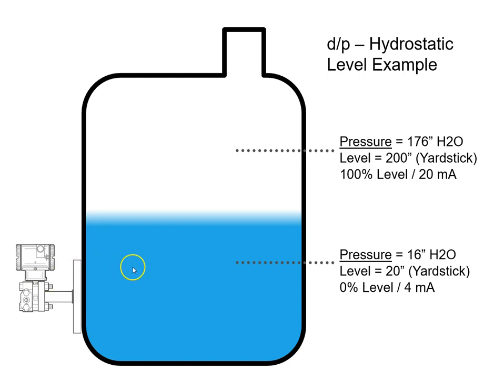As you see in the example, at our low range value, we're measuring 16 inches of water — that's our pressure measurement — and we can convert that into 20 yardstick inches of level. At our upper range value, we're measuring 176 inches of water as a pressure measurement, and then we're inferring the actual level of 200 yardstick inches off of that.